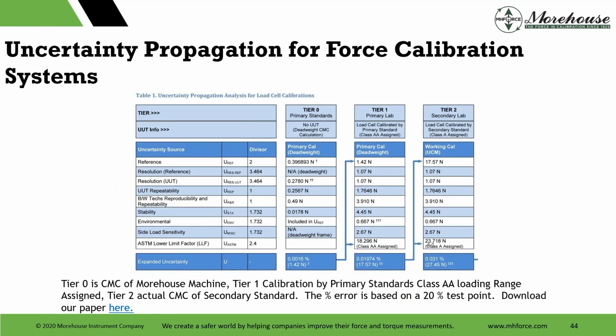And then back in 2017, I wrote a paper using this concept, and here's all the uncertainty sources that we put in. We could have put in some more. We controlled this in our lab. Tier 0, that's dead weight. We were able to get 0.0016. The next tier, when we calibrate that standard with dead weight, the best we could get at the 20% force point was about 0.02%. It says 0.01974, so we're just going to call that 0.02.